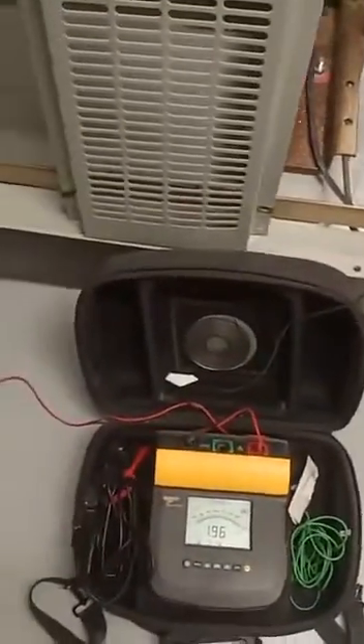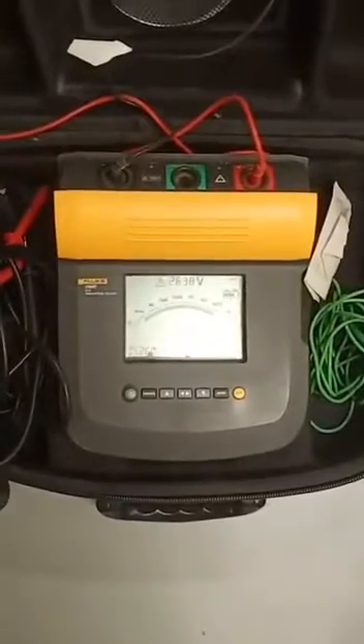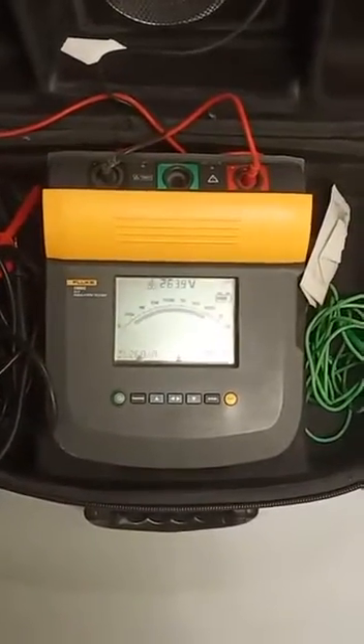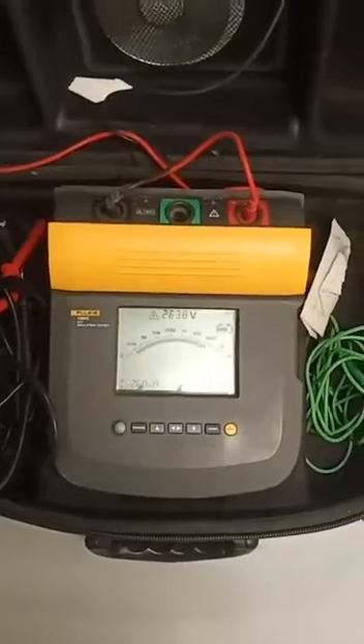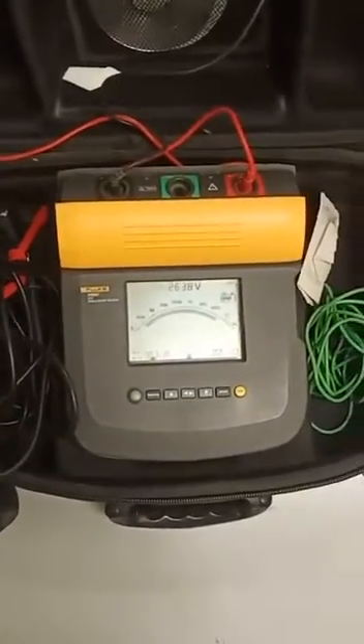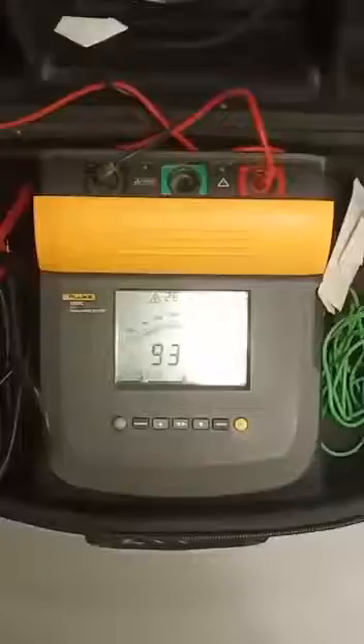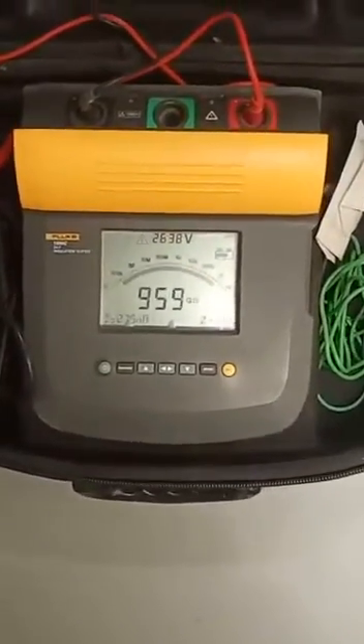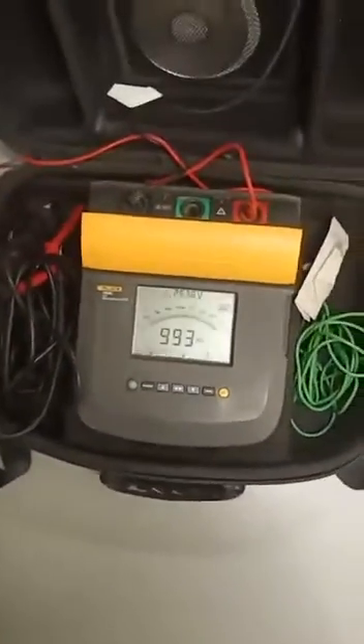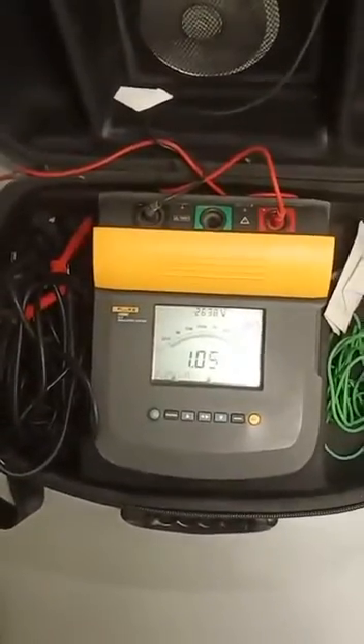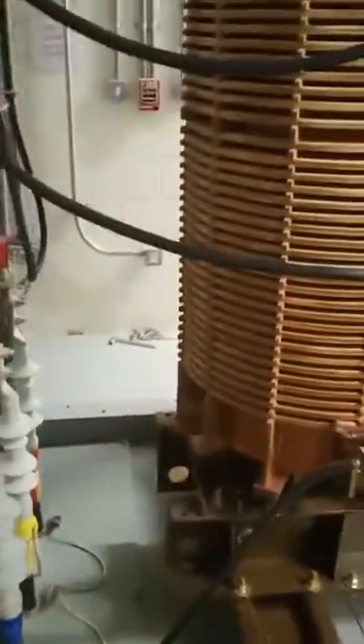We are going to apply 2500 volt. We injected 2500 volt DC. This is the 1 minute result, 959 gigaohm. The test will continue up to 10 minutes to find the PI value. The IR result is in gigaohm. The value is good, meaning the winding insulation is healthy.